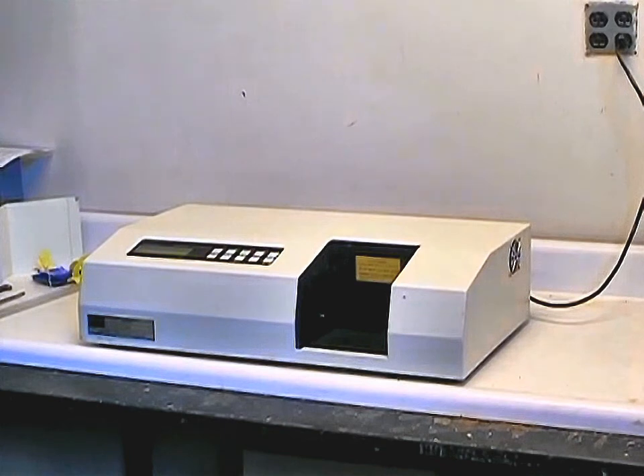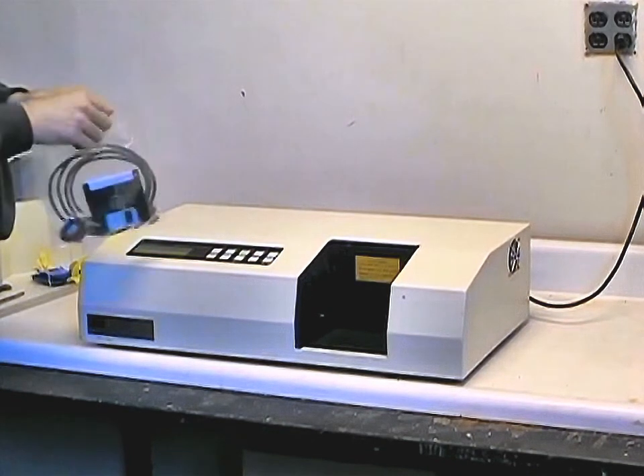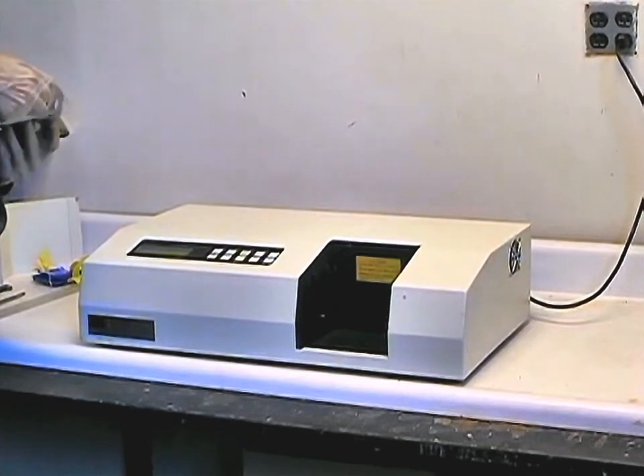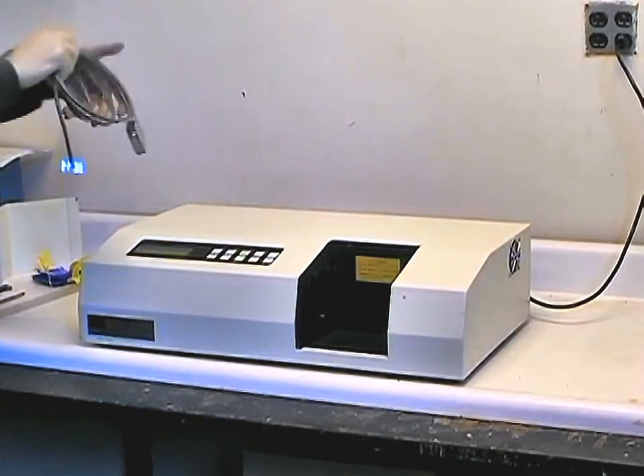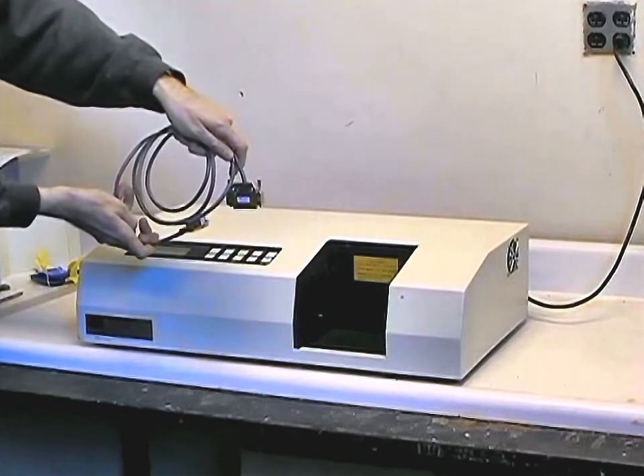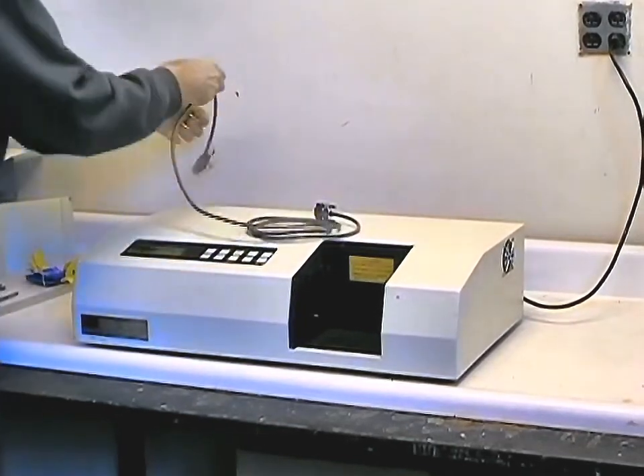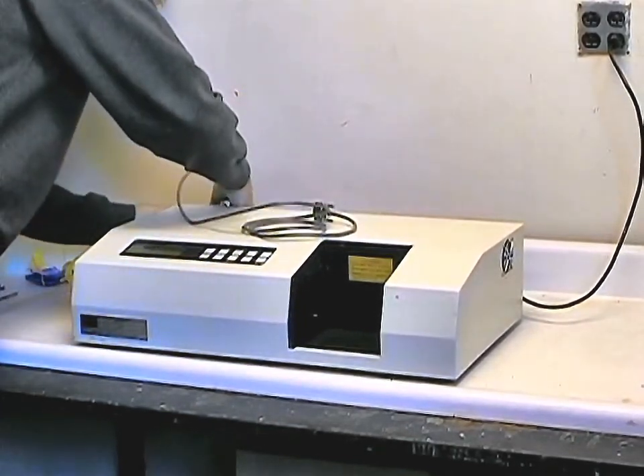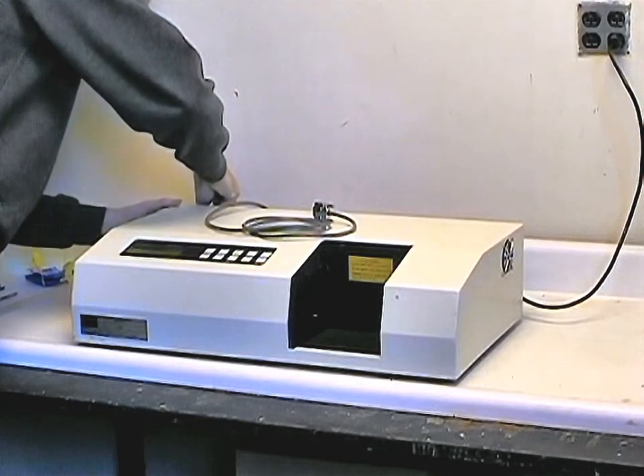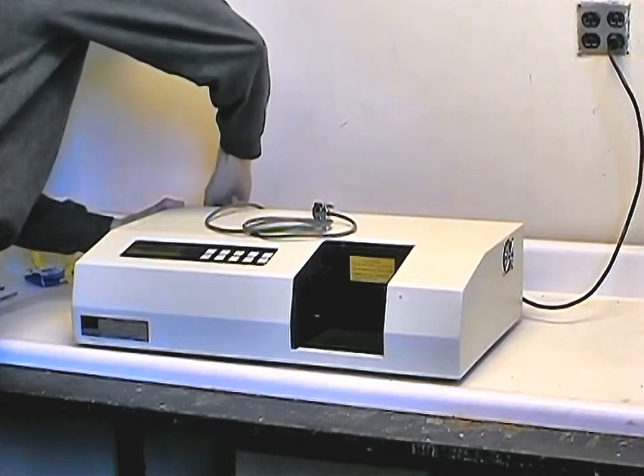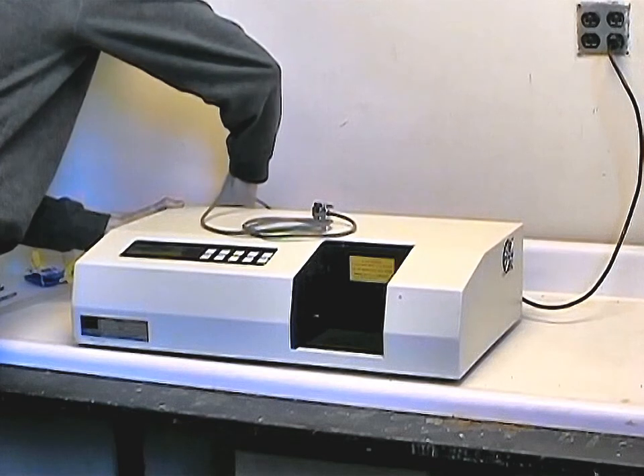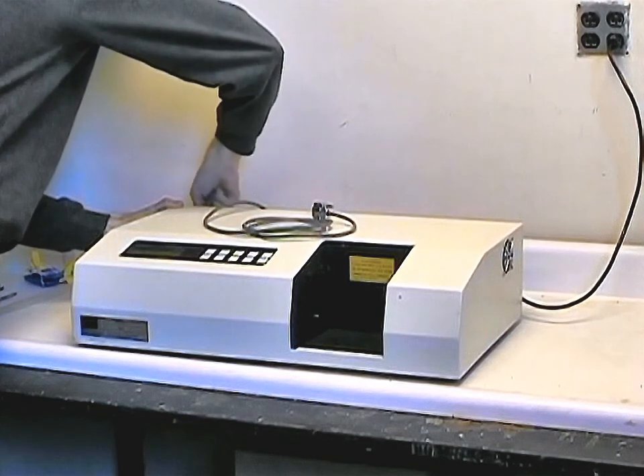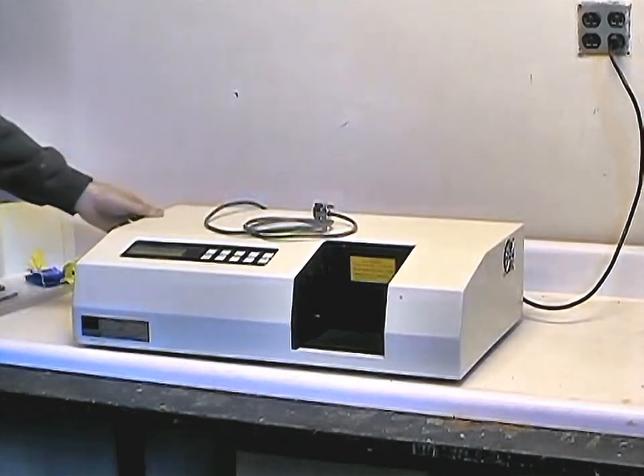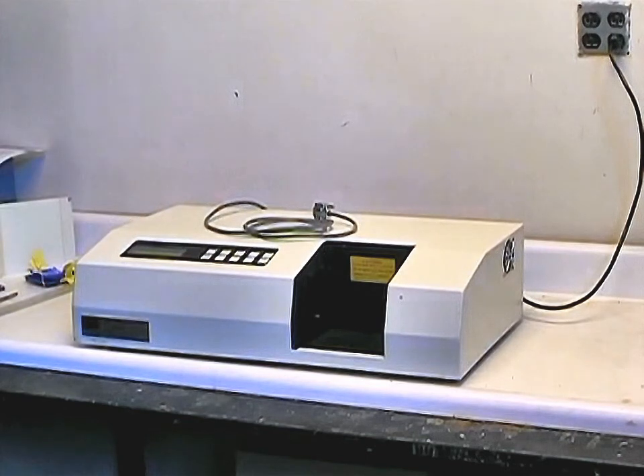There is also a custom-made data cable with a 25-pin connector, which goes to the back of the M500 in the rear left corner. It is recommended that you attach the lockdown screws to make sure you have a good electronic fit, because this is how data is transferred to the PC to generate your spectrum. The other end is connected to a PC, and we will now show how to install the software.